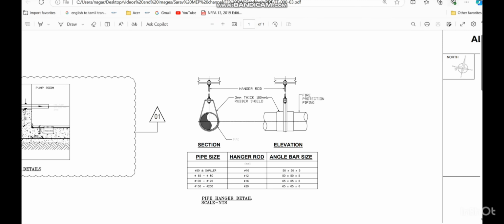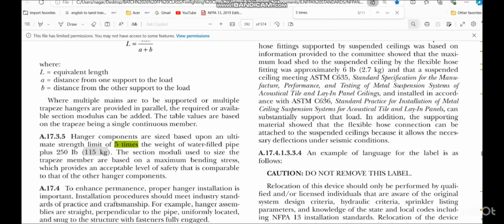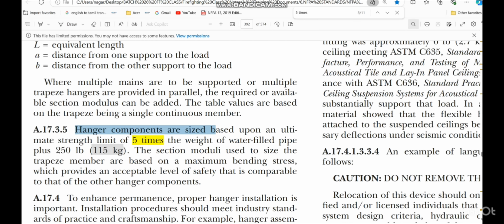The next one, coming to the pipe hanger detail. We must understand one point very clearly written in NFPA 13: hanger components are sized considering 5 times the weight of the water-filled pipe plus 115 kg. In other cases we will not do this type of special requirement, but only for firefighting the special requirement is 5 times the weight of the water-filled pipe. For example, we have the firefighting pipe. When the water is completely filled in the system, let's say that it is 100 kg. So 5 times this weight, for example.